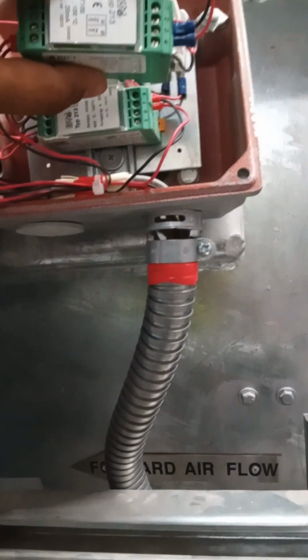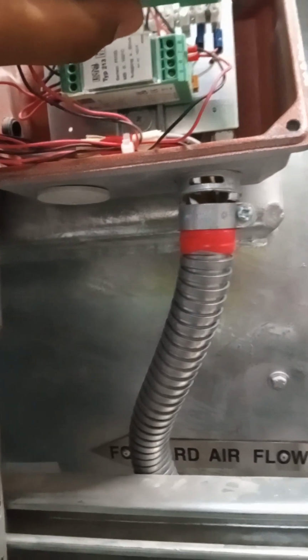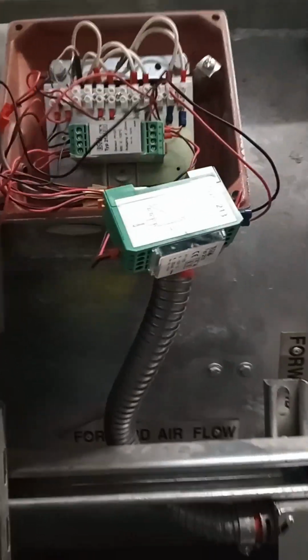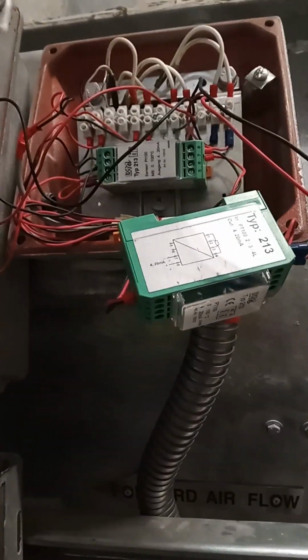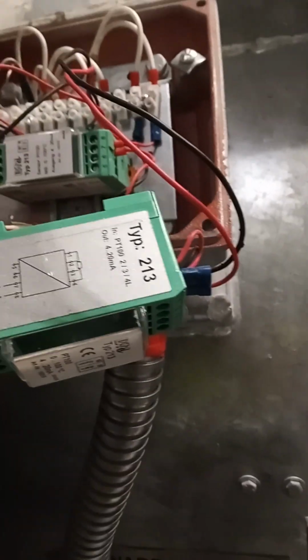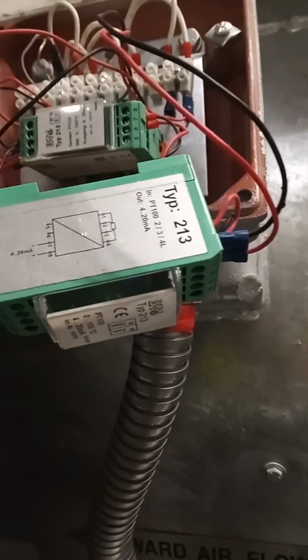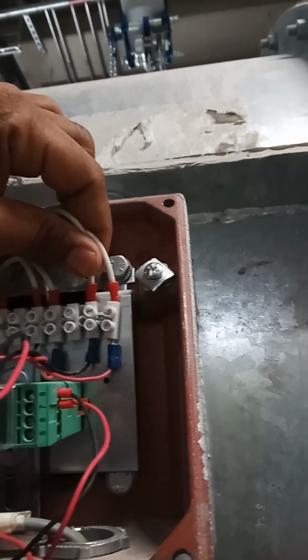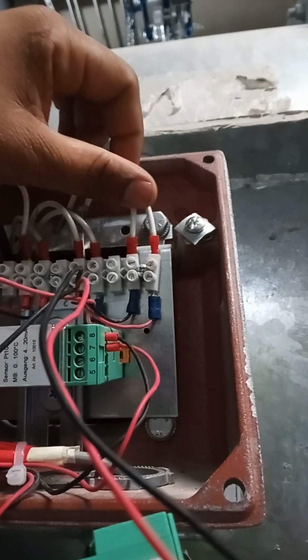There are two sensors. These sensors, transducers, measure temperature values. Two temperature sensors are provided because one is for the east side and the other for the west side. So from this equipment, the TEF fan, these first two cables are for bearing temperature east. So the bearing temperature east value will come here. From here it goes to this transducer.